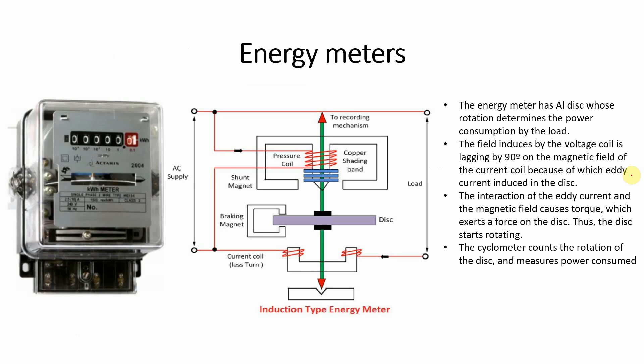Energy meters کے اندر eddy current use ہوتا ہے۔ Energy meter everyday life کے اندر use ہوتا ہے — گھروں میں اور industries کے اندر جو power consume ہو رہی ہے اس کو measure کرنے کے لیے۔ اس کے اندر ایک shiny metal disc ہوتی ہے جس کی motion کی وجہ سے جو power consume ہو رہی ہے اس کو record کیا جاتا ہے۔ Energy meter has an aluminium disc whose rotation determines the power consumed by the load. The field produced by the voltage coil is lagging by 90 degrees on the magnetic field of current coil, because of which eddy current is induced in the disk.